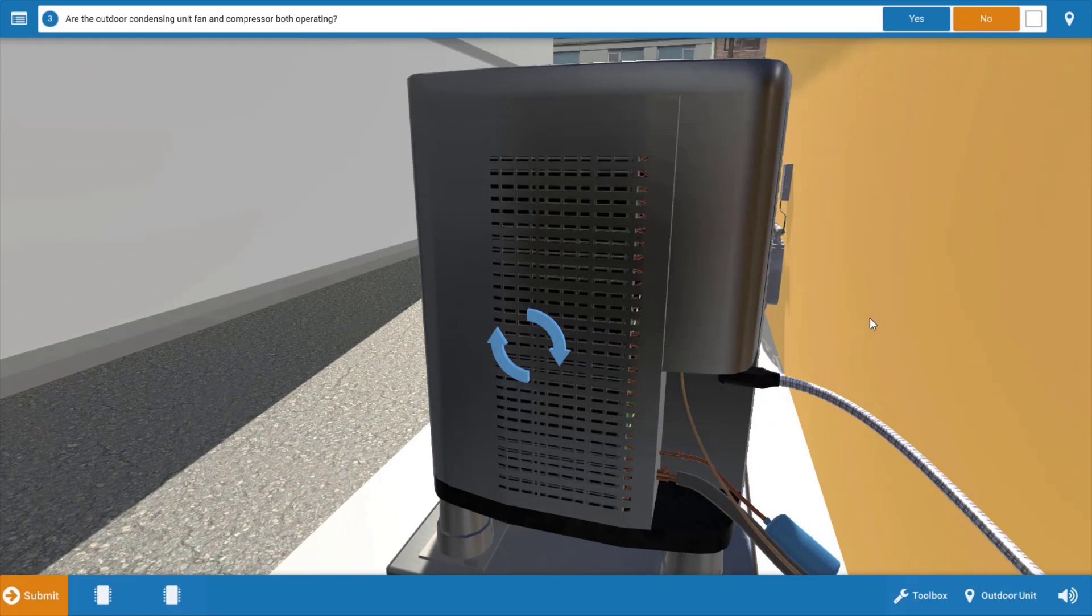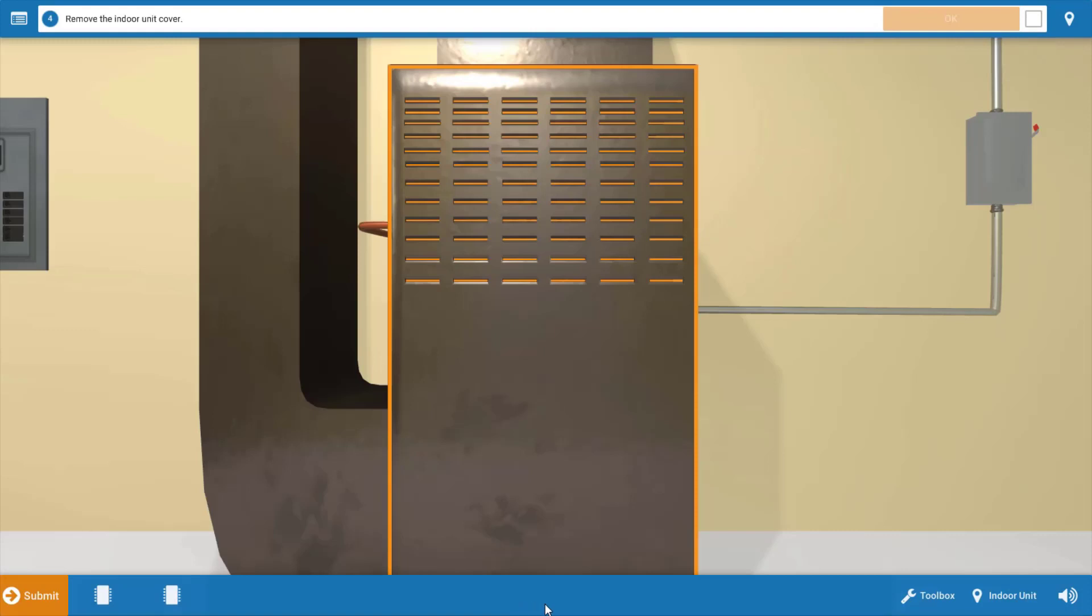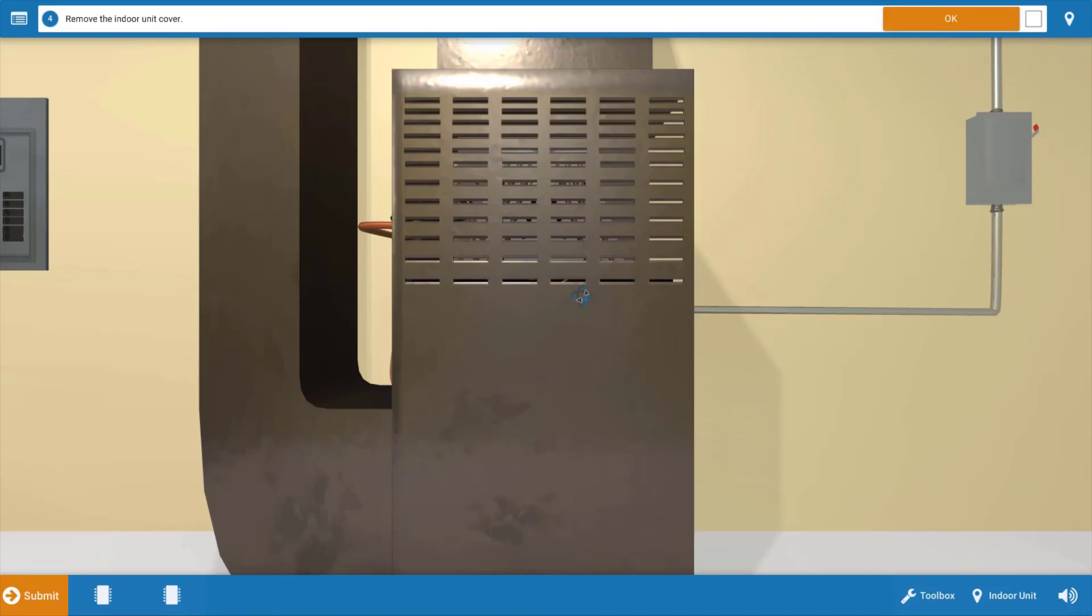Now for further verification of the compressor, you can always attach a clamp-on ammeter to one of the wires leading to the three-phase motor in the compressor to determine if it's actually running or not. Now after we've determined that none of the motors are running, we're going to go back to the indoor unit and remove the cover from it.